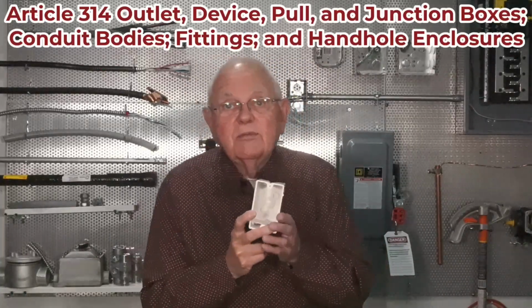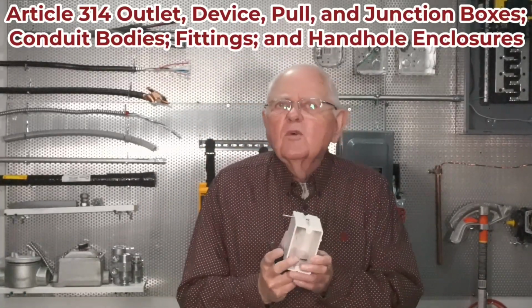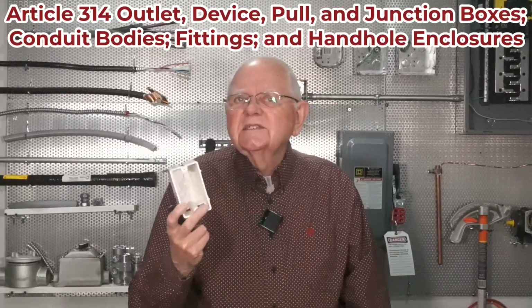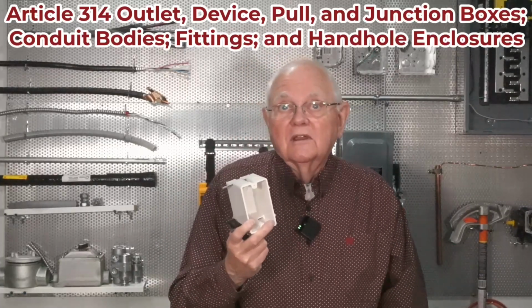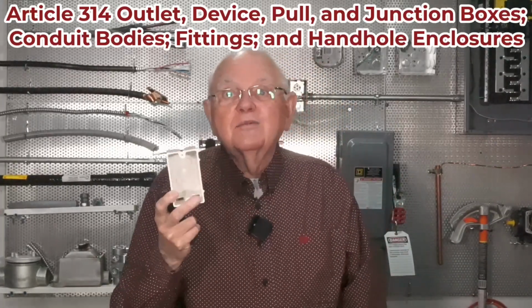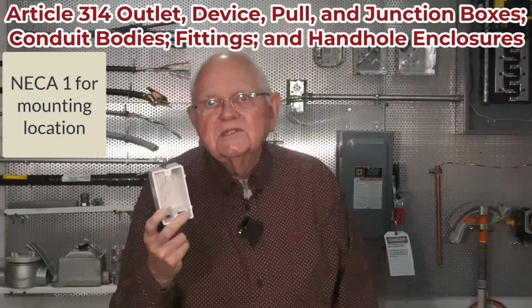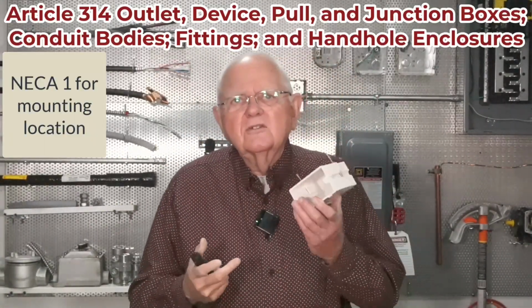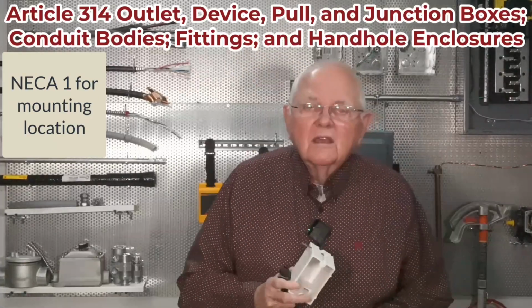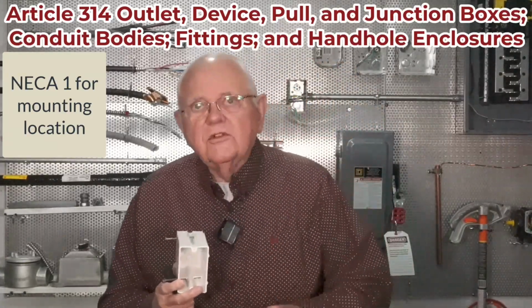Conductors, wires, and cables are talked about in NECA 1. It says maintain minimum bend radiuses, use compatible connectors, do not mix dissimilar metals, all those things that are pretty much common sense to us. There's going to be a lot of information in the NEC about installation of boxes. But once again, back to my door example, it doesn't tell me even which side of the door to put it on. Well, we pretty well know we're going to put it opposite the hinges, aren't we? That would make sense. We want to put it close to the trim. How close to the finished trim, wherever that's going to be? About 2 to 12 inches from the trim, 3 inches from the door frame.